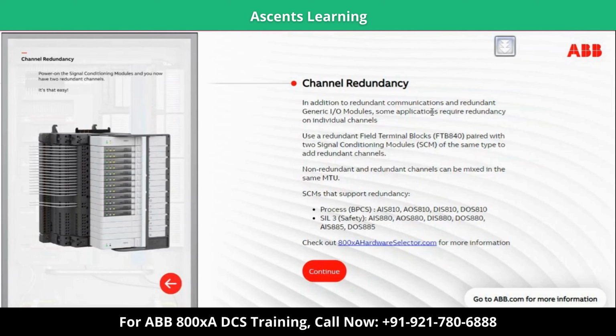or in addition to redundant communication and redundant generic input output module, use of redundant field terminal blocks are also paired with two signal conditioning modules of the same type added redundant. So field terminal block units can also be made redundant in the ABB system or any other DCS also. They support this channel redundancy.